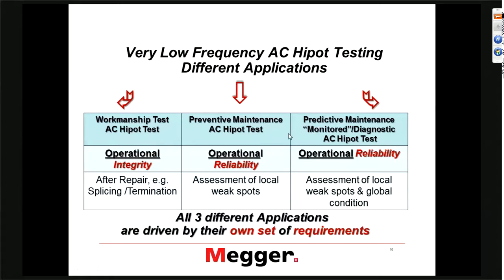I can do a preventive maintenance test. In contrast to operational integrity, it gives operational reliability information because if it passes the test as prescribed in 400.2, it's typically an indication that the aging condition is at a level that allows me to operate this cable for another three or four years before I should retest it. So this is preventive. Now we can go to the predictive maintenance test, which is a monitored or diagnostic type test, giving me insight about the operational reliability of the cable.